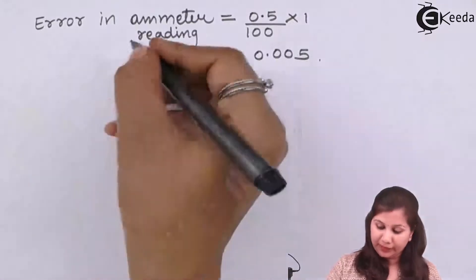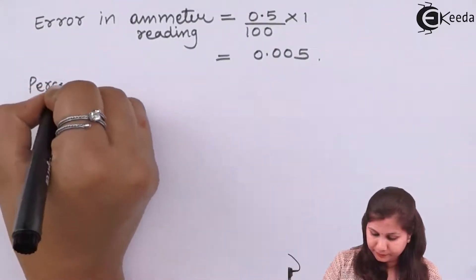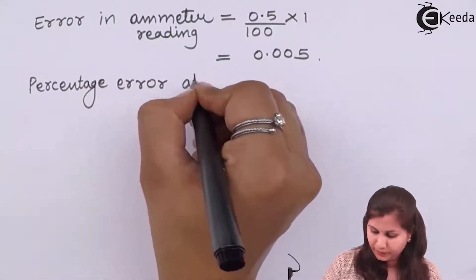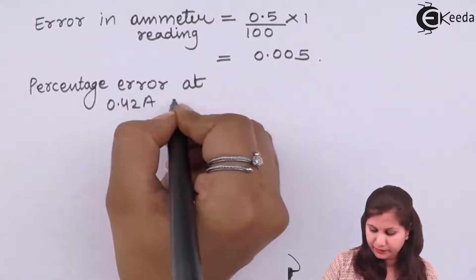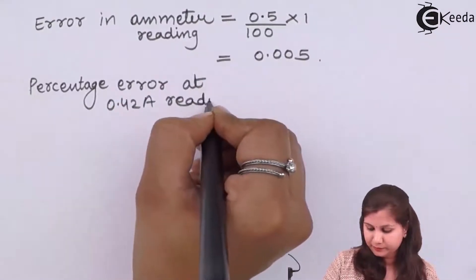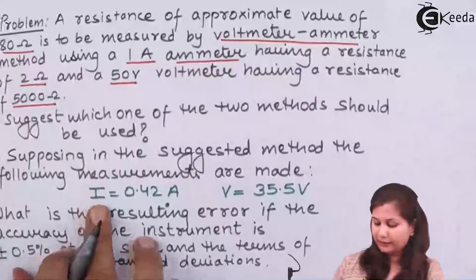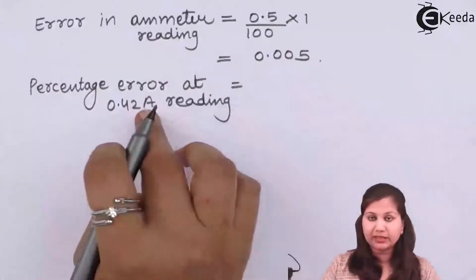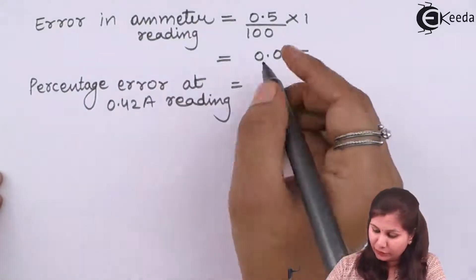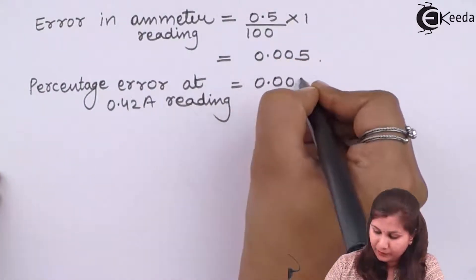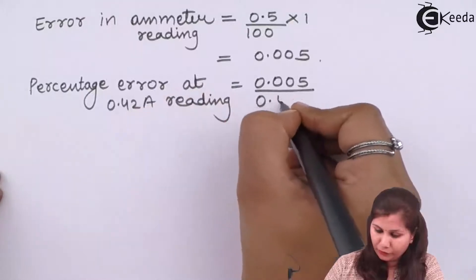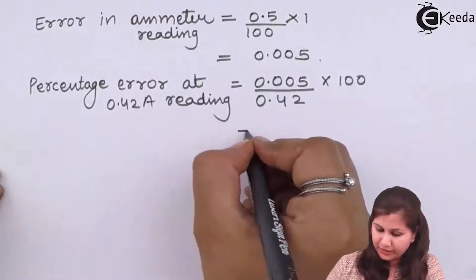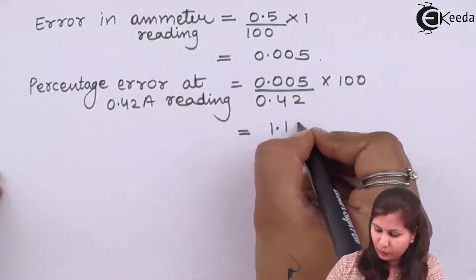Now if we calculate the percentage error at the 0.42 ampere reading, because the meter is giving us a reading of 0.42 amperes, the percentage error is 0.005 divided by 0.42 into 100, which comes out to be 1.19 percent.